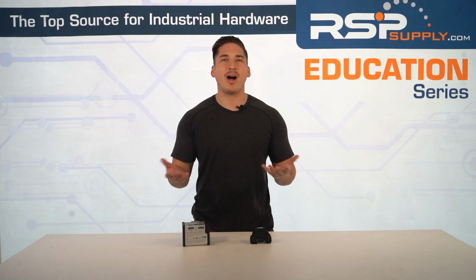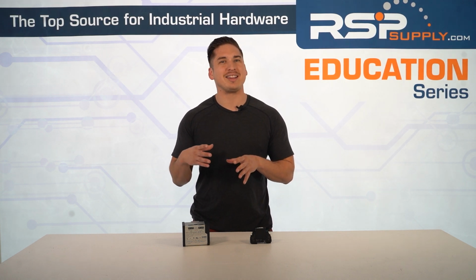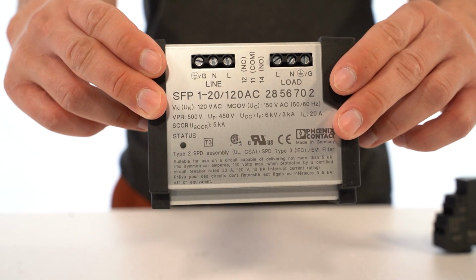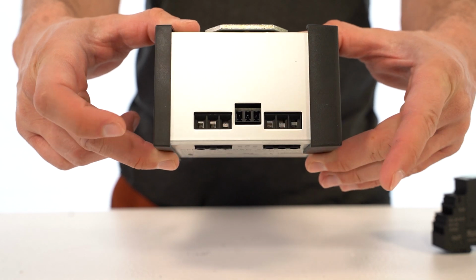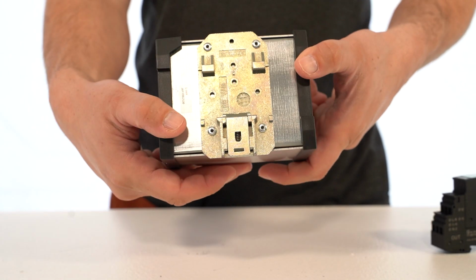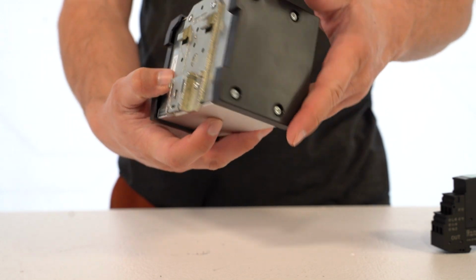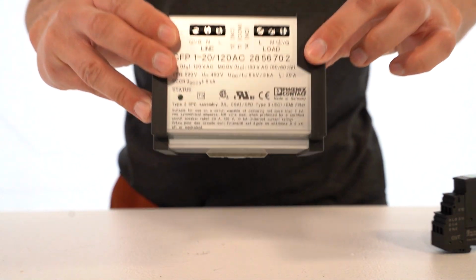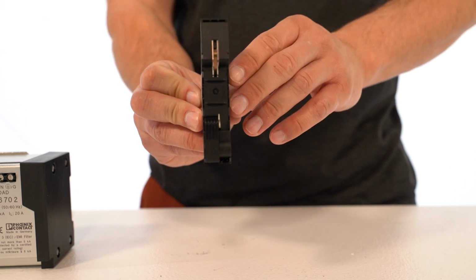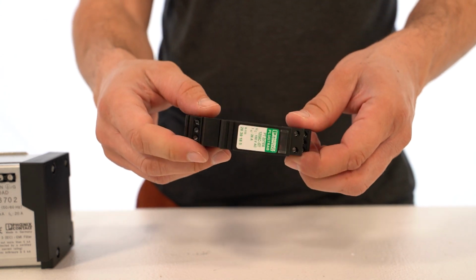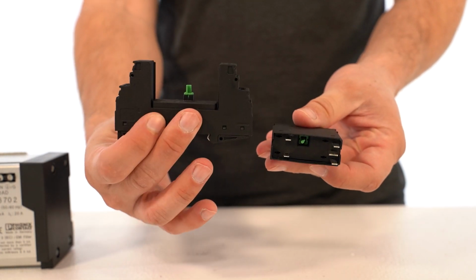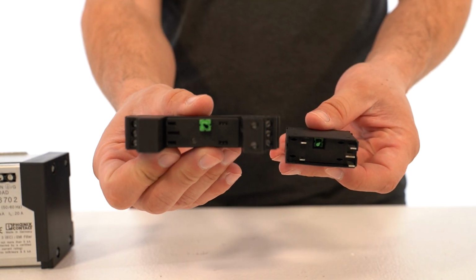A big question is, why surge protection in control panels? Within control panels there's a whole ton of really sensitive components, and first and foremost we want to keep these valuable components safe. You'll see a power surge protection device right here by Phoenix Contact, which shields critical hardware like PLCs and VFDs from overvoltage damage. Data surge protection, on the other hand, keeps your communication lines intact, preventing damage to devices responsible for critical data exchange like HMIs, SCADA systems, and PLCs.